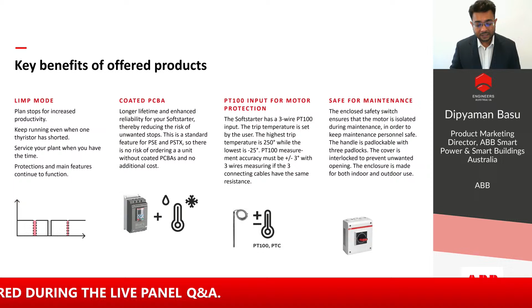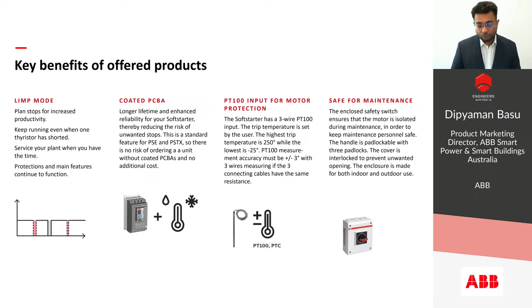With the help of the PT100 input, we're also able to trip the circuit when required, and the user can set the temperature where the trip needs to happen, right from minus 25 degrees Celsius all the way up to 250 degrees Celsius. And when we talk about planned or scheduled maintenance, ABB's enclosed padlockable solutions with our switches can isolate a motor or a motor control system during maintenance for the safety of the operating personnel. These switches have been tested for both indoor and outdoor use.